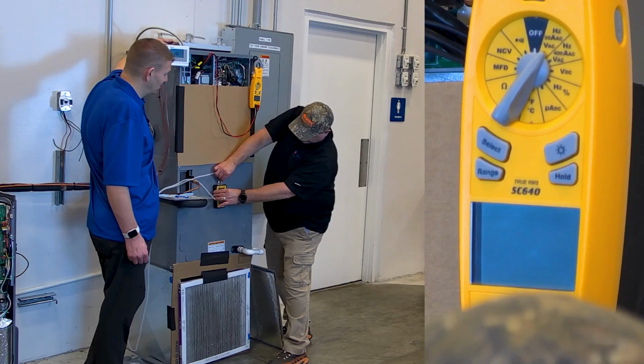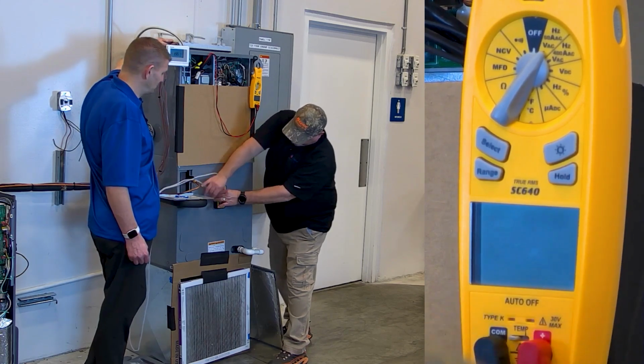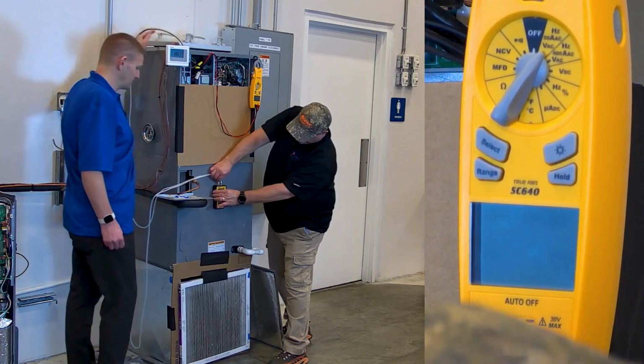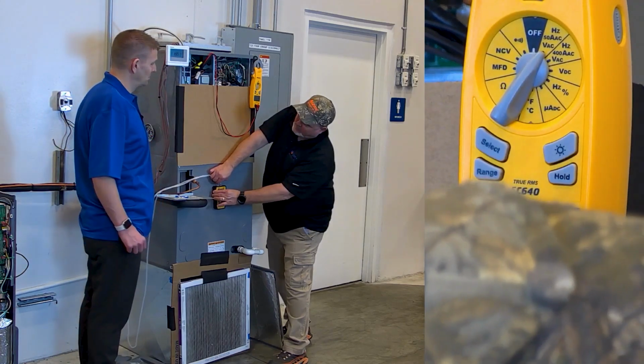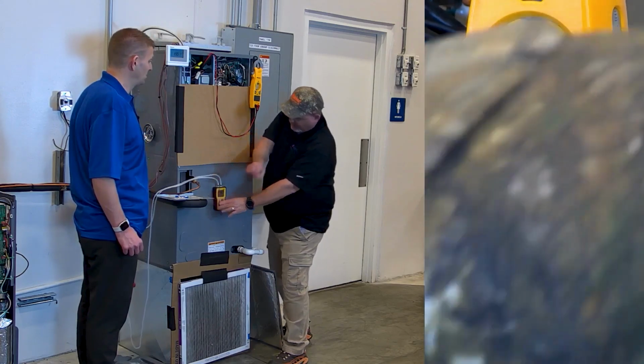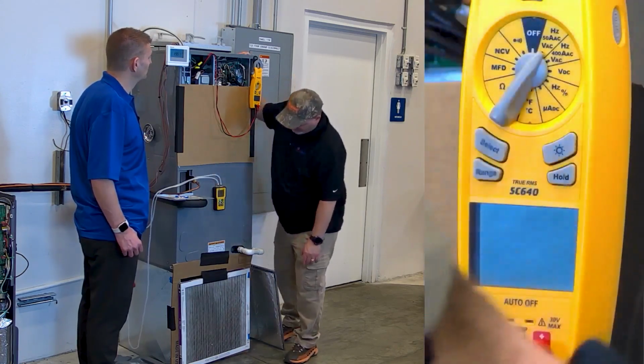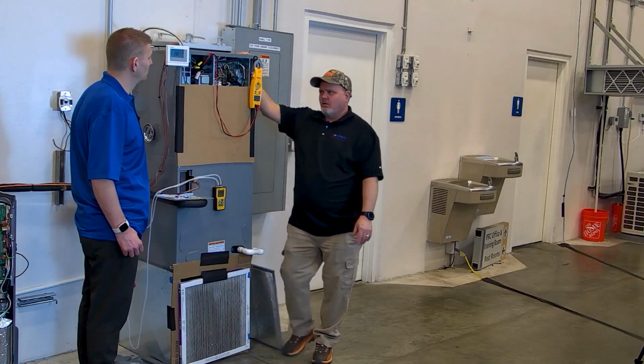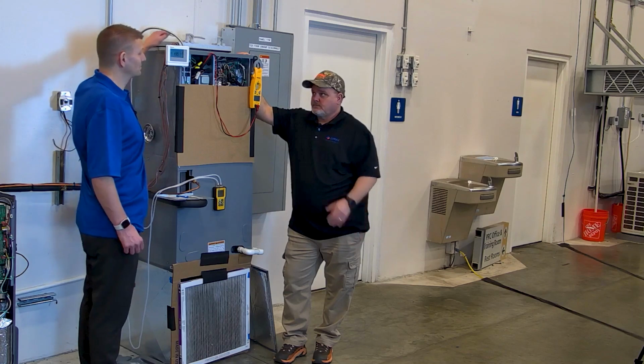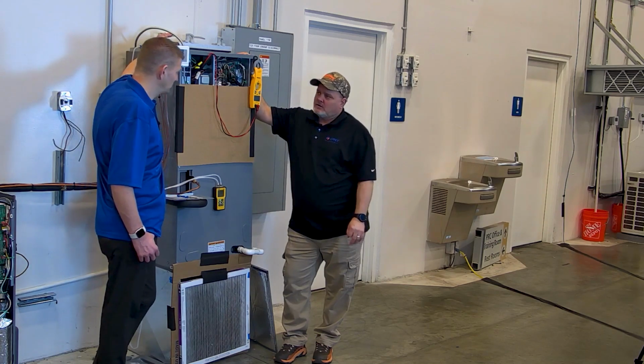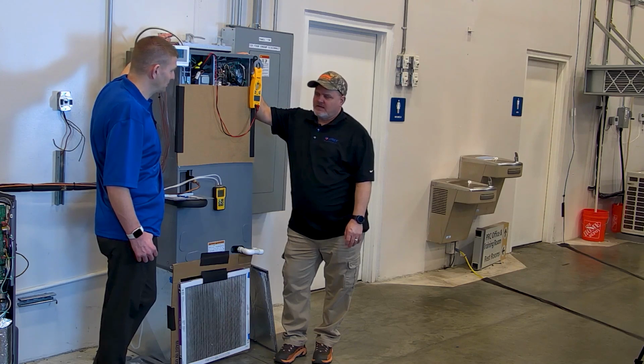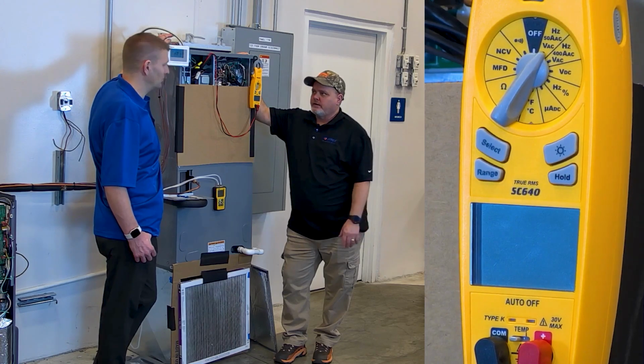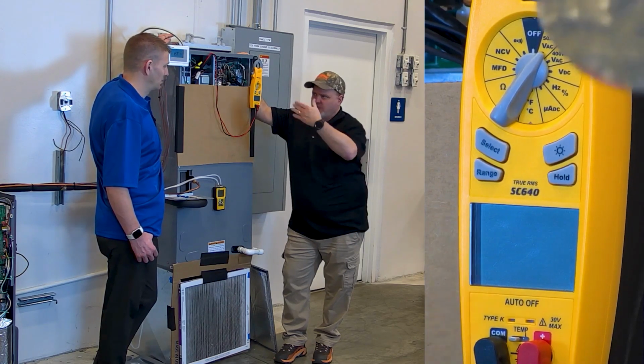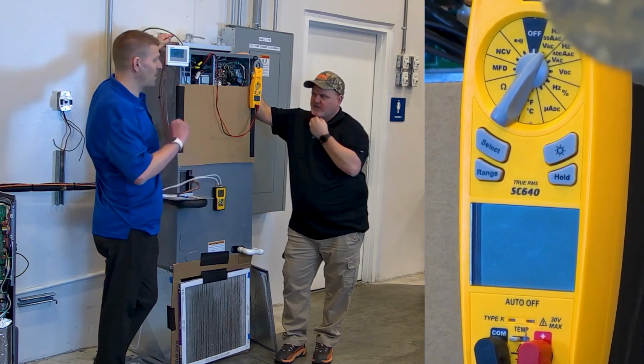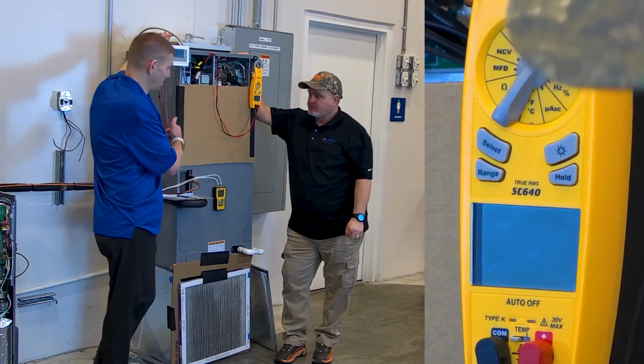Here comes the blower. Blower just came on after the coil heated up. I don't think it really delays because of the coil heating up, though, does it? No, I don't believe so. It's not on long enough. The unit's not running long enough for it to really heat up that coil. It was warm coming out right away. So maybe with RS485 it does delay a little bit. Right. It's not significant though. Because I seen with the 24 volt, it was pretty quick. The blower came on, but it was slowly ramped up, where this came on almost right away.